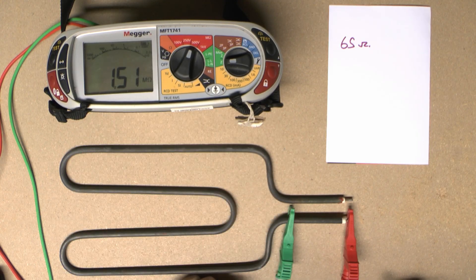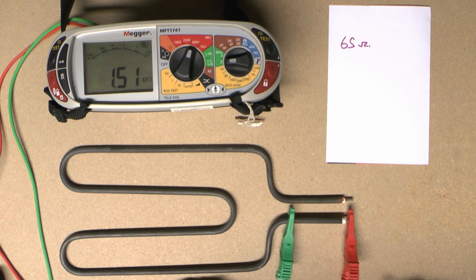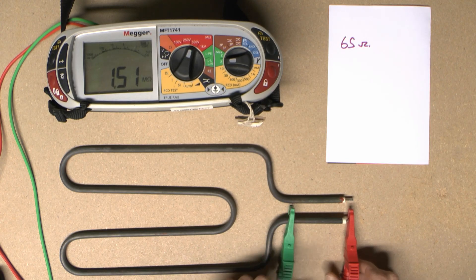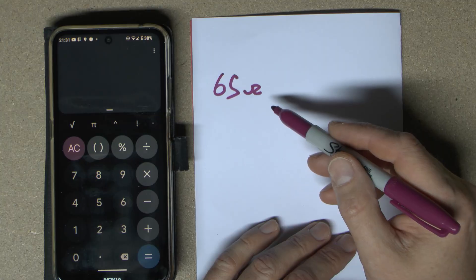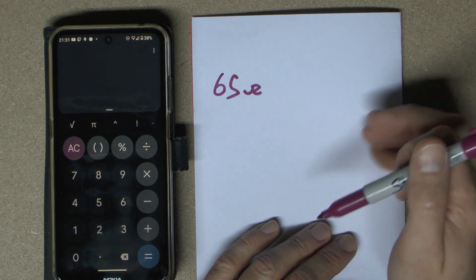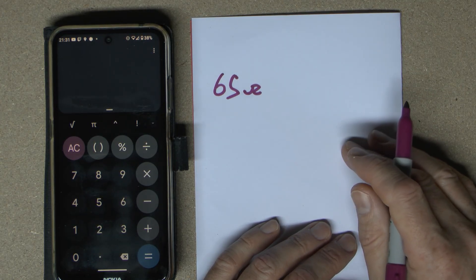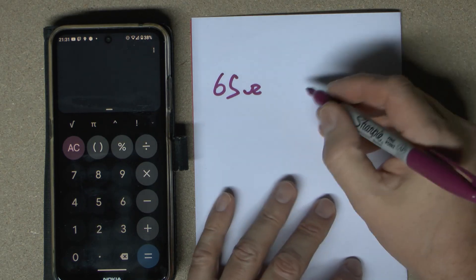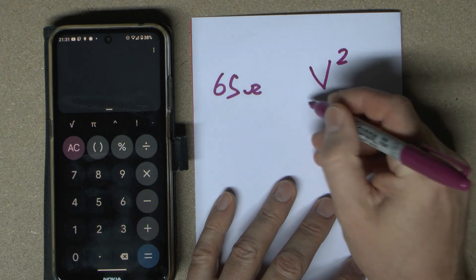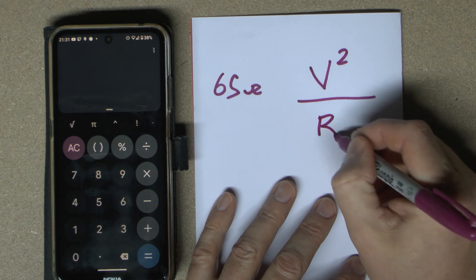If it comes up as shorted, or around 0.1 mega ohms or something, then the element is faulty and needs to be replaced. The resistance depends on the power of the element, and you can use a quick calculation to get an idea of what the power was. That should be within the realm of what you'd expect. The formula is voltage squared divided by the resistance.